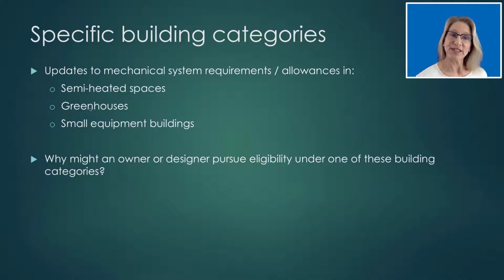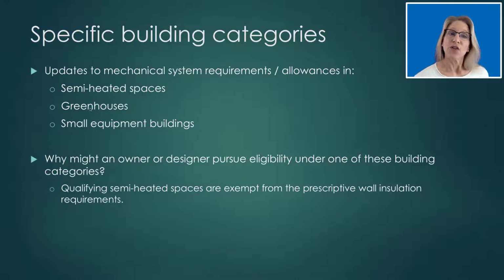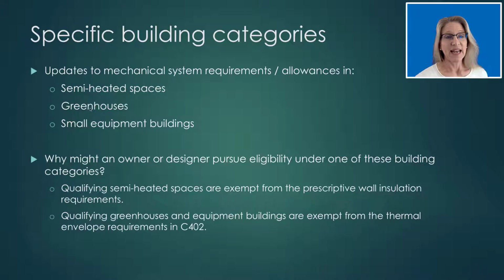So why might an owner or designer pursue eligibility under one of these building categories? For a qualifying semi-heated space, they are exempt from the prescriptive wall insulation requirements. So if the architect or building owner would like to avoid that requirement in their building, then they do need to coordinate with the mechanical engineer or contractor ahead of time to make sure that the systems that are going to be installed meet the criteria so that the building would be eligible as a qualifying semi-heated space. And qualifying greenhouses and equipment buildings are exempt from all of the thermal envelope requirements in Section C402.